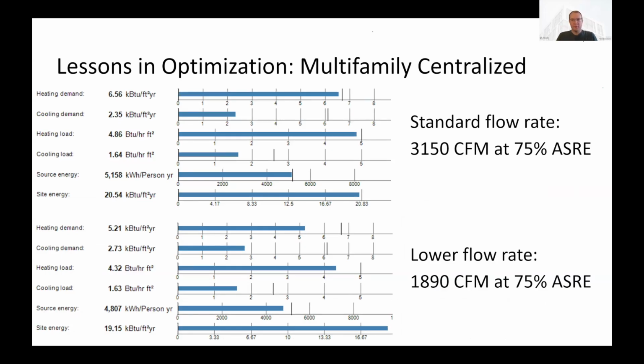All right, let's look at some multifamily buildings first. So this is a quick aside that the flow rate can matter a lot in multifamily buildings. Small changes in units can have big impacts over the building. And so we've seen this happen before as we reduce airflow rates. Even if we don't change the apparent sensible recovery efficiency, the fact that we just have less air being moved, less makeup heat that we have to introduce into the building, gives us pretty large benefits. So we can look at our heating demand at the top here. It's pretty tight on the certification criteria, same with the heating load. If we're able to reduce our flow rates, we can get that down and remain in a buffer on our PHIUS criteria.